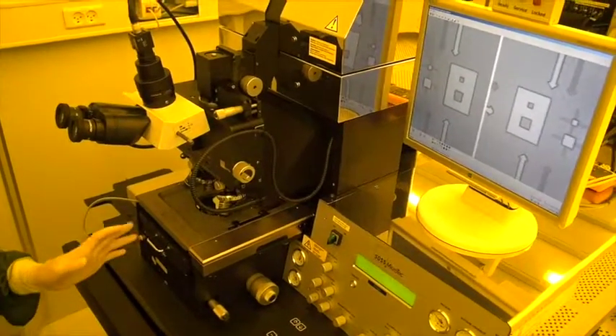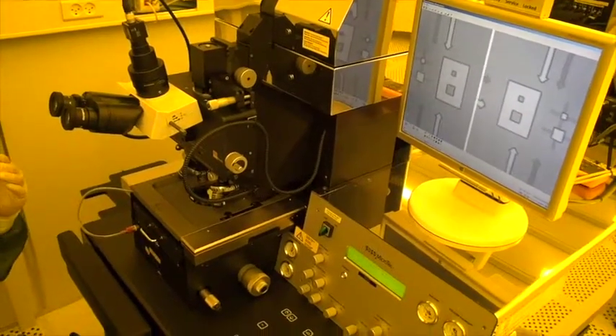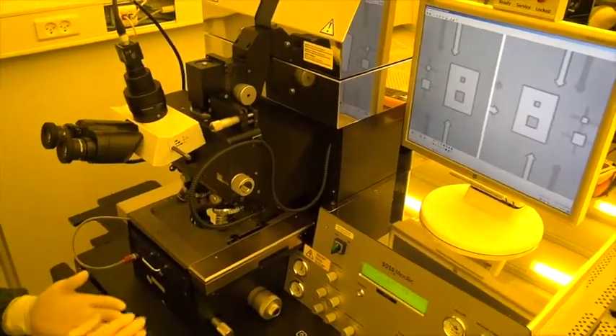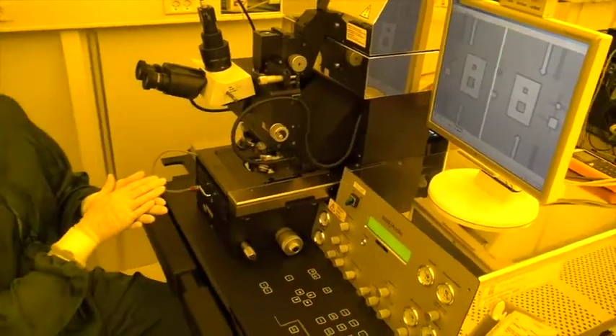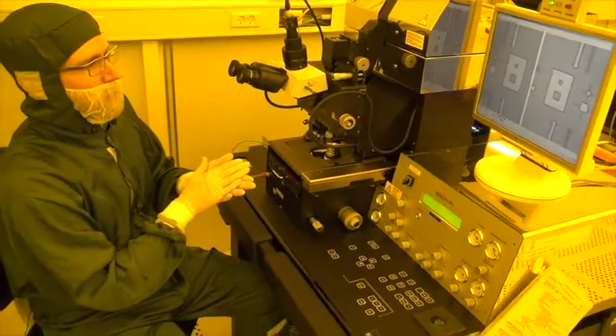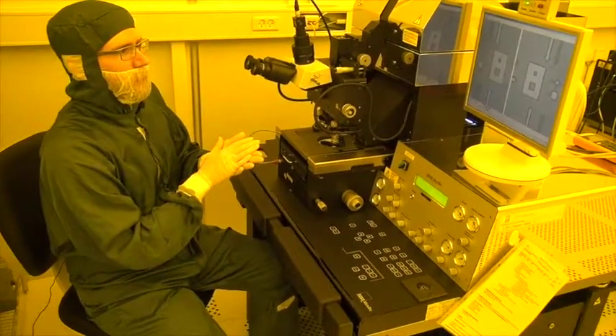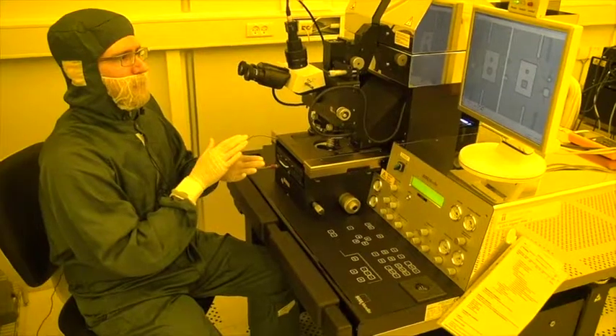When I'm satisfied with the alignment, I can do an alignment check, which means I can bring mask and substrate into contact as it would be during exposure in order to check that the alignment is perfect.